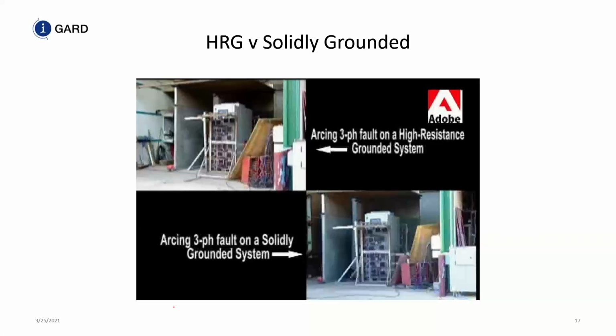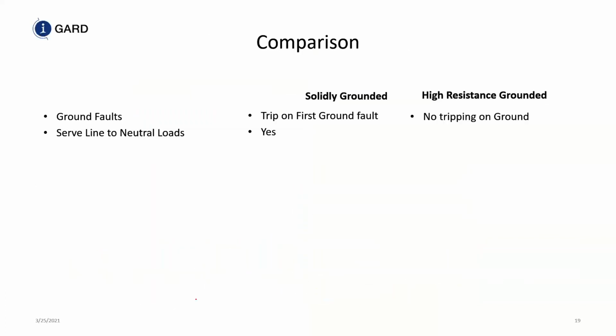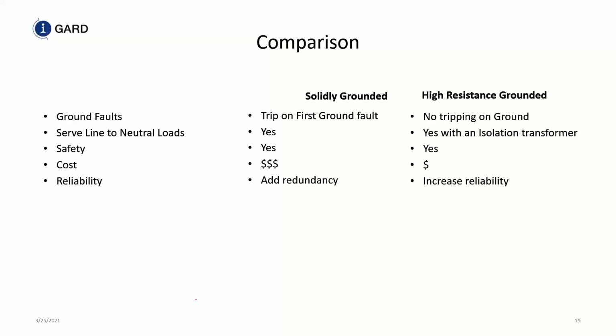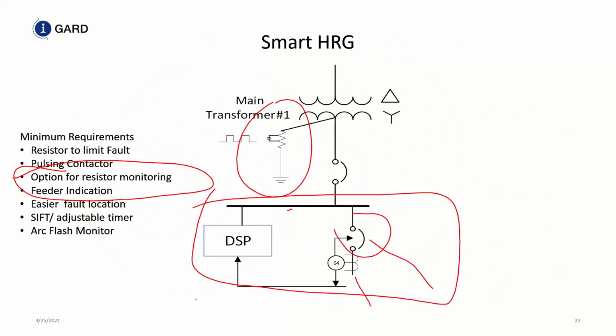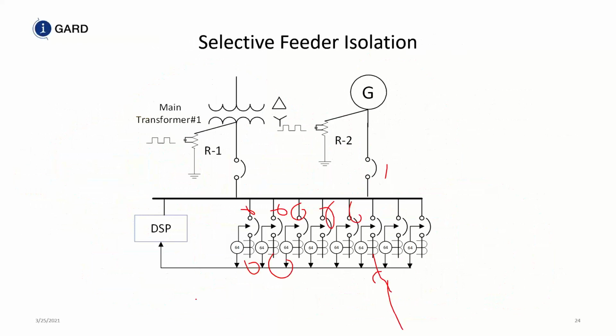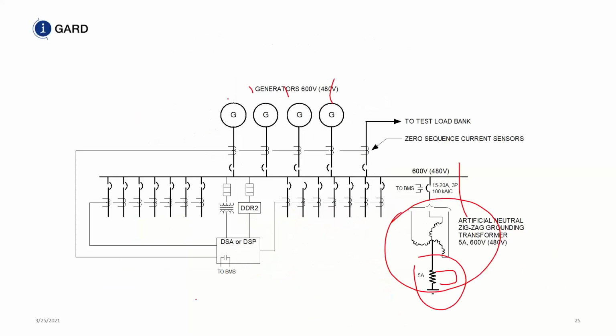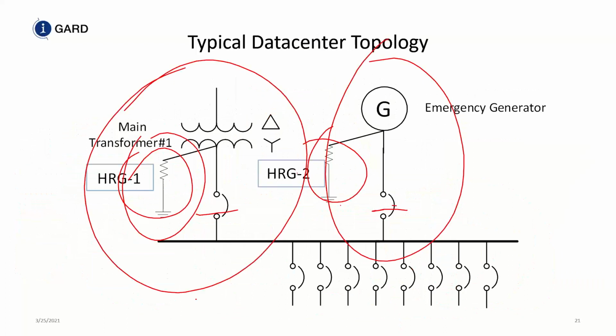Next question is, for the typical data center topology, does the generator need a fault detection system as well? Is it not redundant if there is one for the main transformer? The HRG on the generator is purposed for reducing the high ground fault current a generator can undergo?